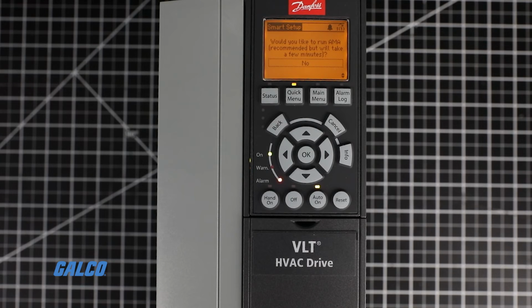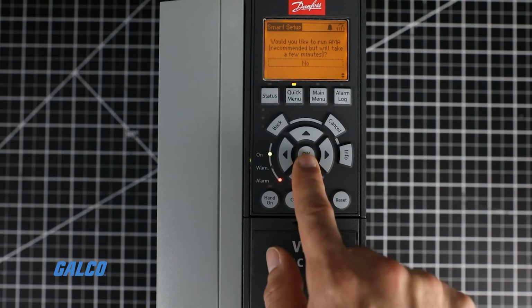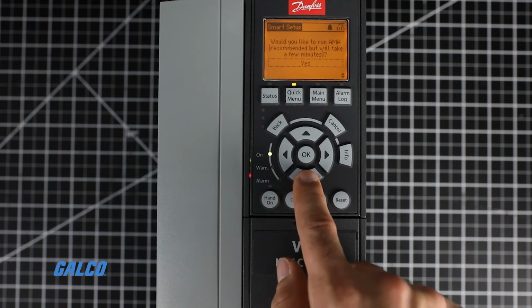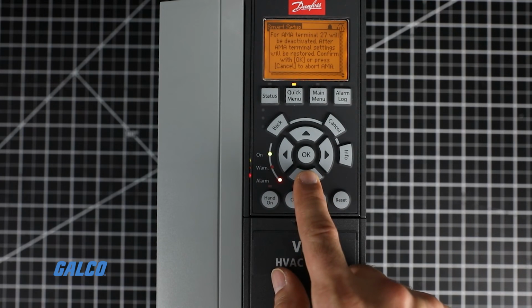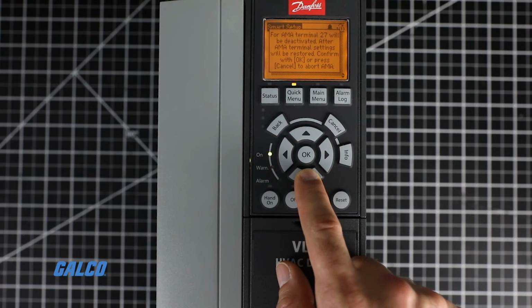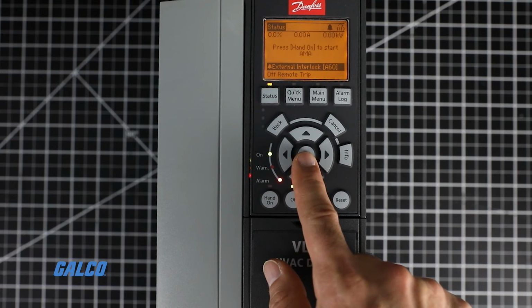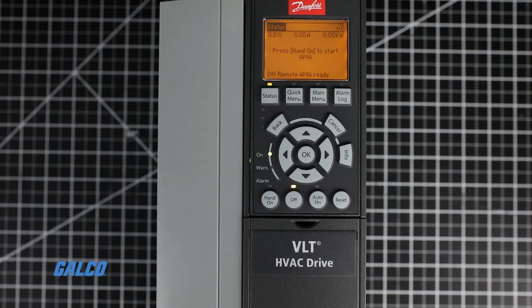Your next step will be to run an auto-tune. On the FC102, this is called automatic motor adaption, enabled at parameter 1-29. To do this, enter Enable Complete AMA and press OK. The drive will tell you to press the hand-on key. Do so, and the drive will perform the tuning process. When the AMA is finished, the quick setup is complete.